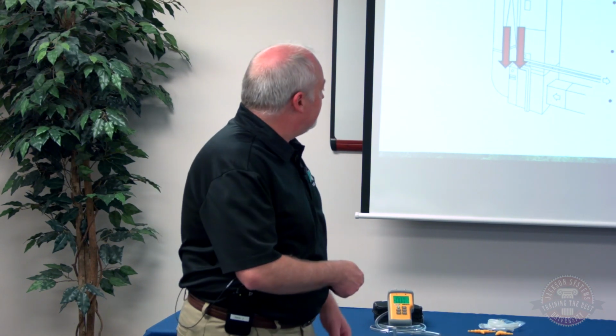If I find out that I've got 2/10 of an inch drop across that air filter, I need to figure out, do I need to add another return somewhere else in the house to draw air from? Maybe they've got just a 1 inch filter and they go down to the big box store and buy that electrostatic filter that's got a tremendous amount of drop through it because they've got allergies.